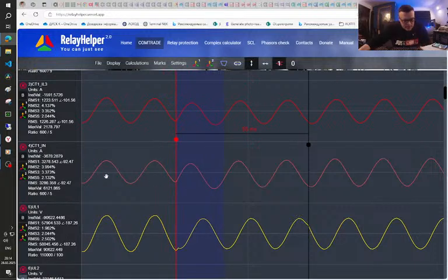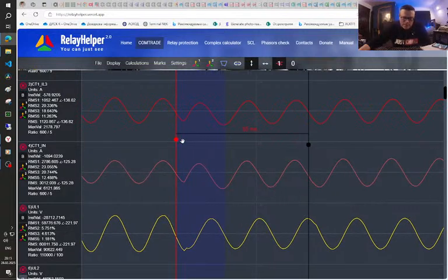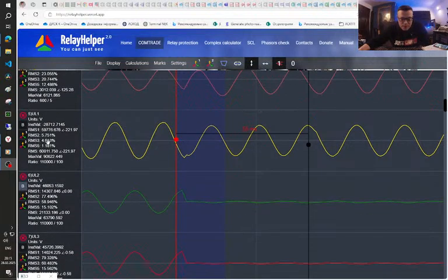This is a little movement of the phasor, and the relay sees that as second harmonic, and you can see here that it was something around 23%, but the setting for that blocking was low enough, something around 20%.